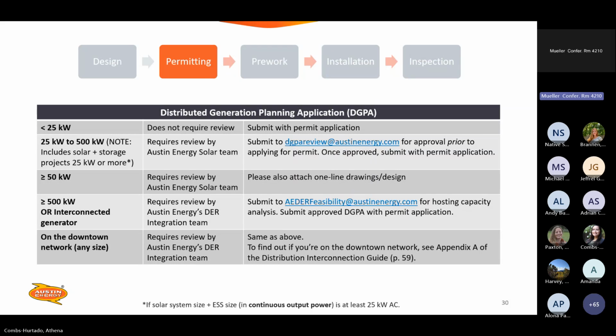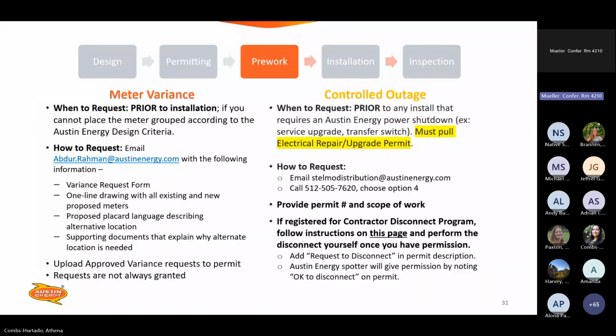Not that common is installing systems on the downtown network of any size. There are quite a few other rules regarding installing on the downtown network. So this will every time require a review by our engineering team, the DER integration team, same as above. To find out if you're on the downtown network, see Appendix A of the Distribution Interconnection Guide, and that will tell you. And lastly, if solar system and ESS size is at least 25 kW, that's an asterisk around. Yeah, so add up the kilowatts, not the kilowatt hours. That's what we're concerned with: kilowatts of both your solar and your battery.